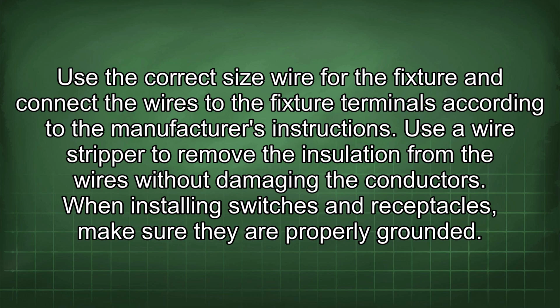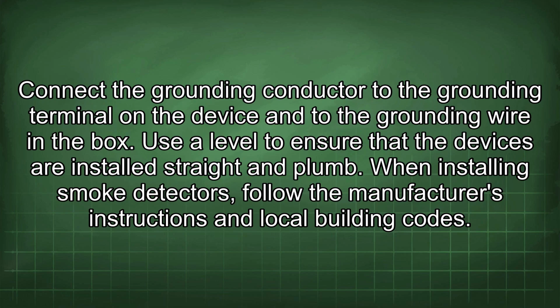When installing switches and receptacles, make sure they are properly grounded. Connect the grounding conductor to the grounding terminal on the device and to the grounding wire in the box. Use a level to ensure that the devices are installed straight and plumb.